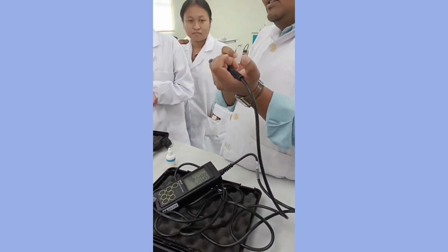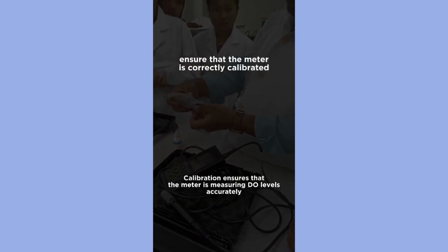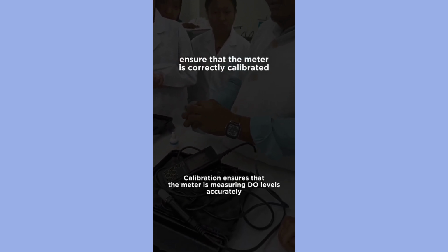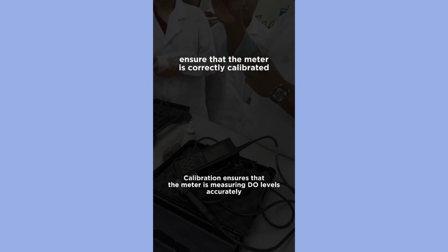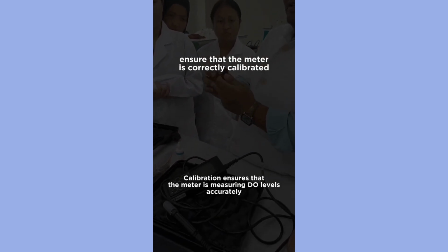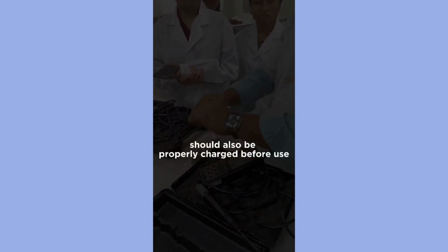Dissolved oxygen meter. I'll be explaining the details on how to maintain the DO meter. Before using the DO meter, you need to ensure that it is set up correctly. First, ensure that the meter is correctly calibrated. Calibration ensures that the meter is measuring dissolved oxygen levels accurately. Next, fill the dissolved oxygen probe with the electrolyte solution to ensure proper conductivity of the electrode. The meter should also be properly charged before use.